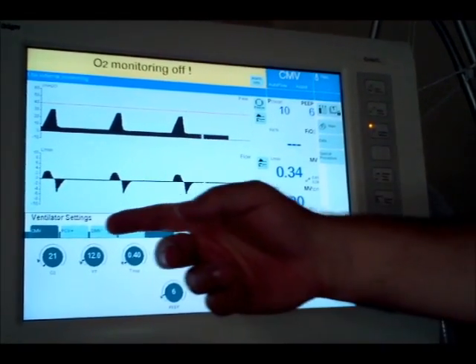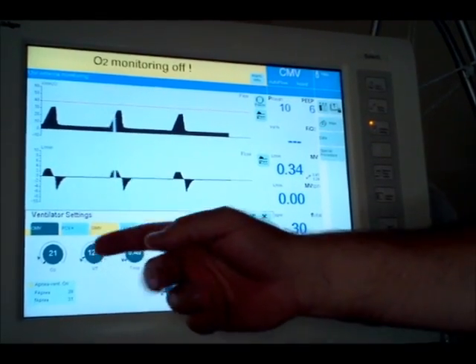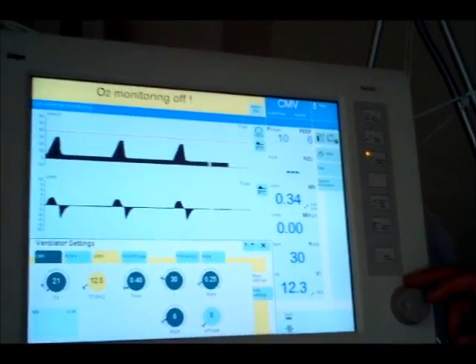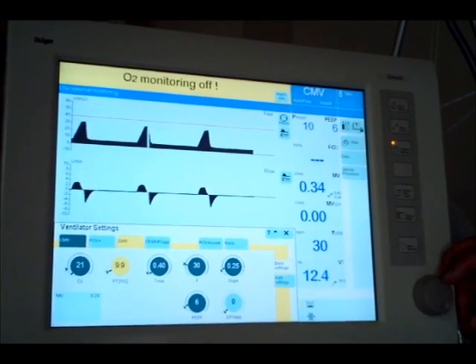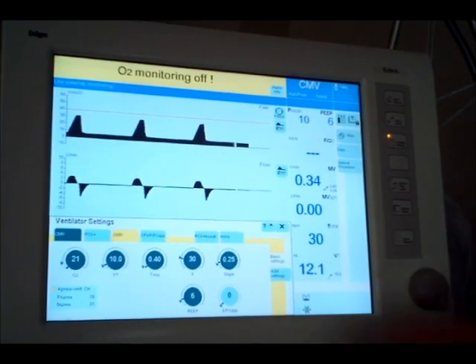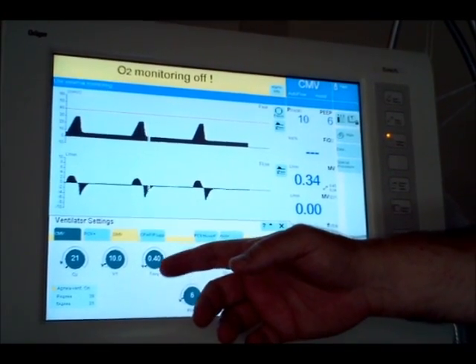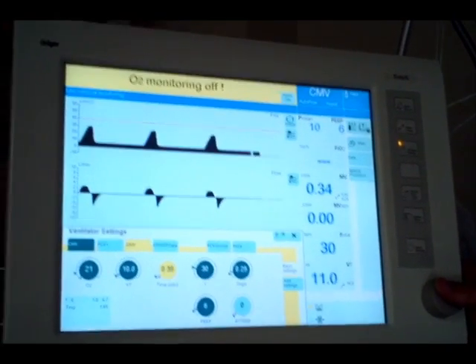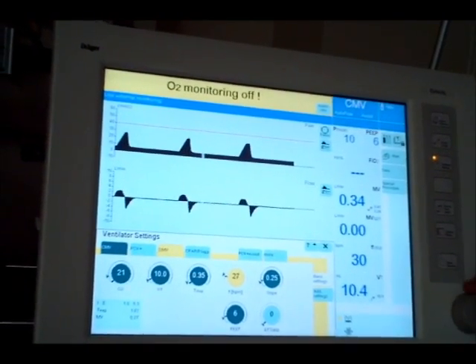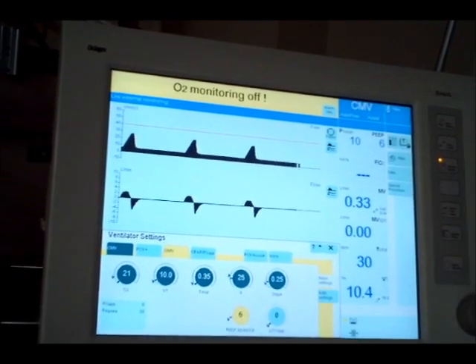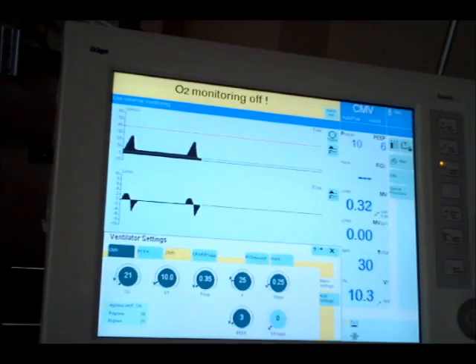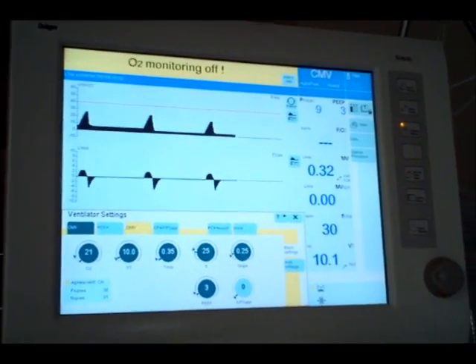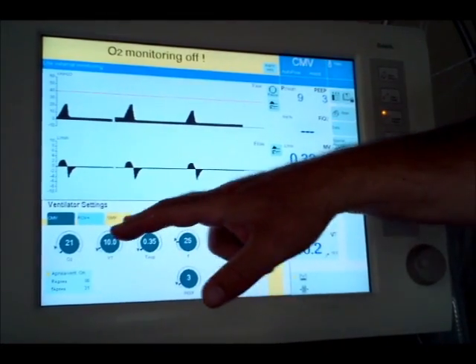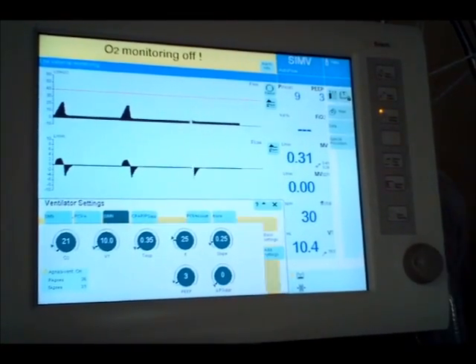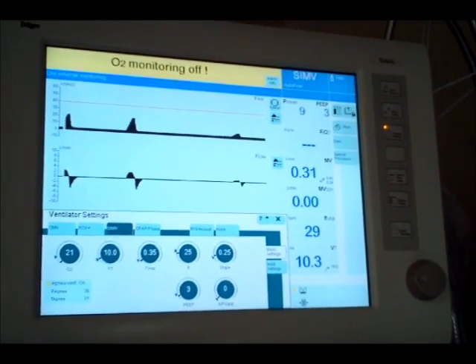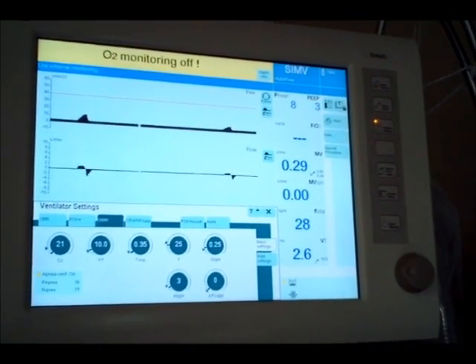Spent too much time talking. I don't have the yellowness anymore. So tidal volume 10. And that changed. Did I say 0.35? I'm trying to go by memory. Yes. 25. Yes. I said 3 here. Yep. Okay. This is where if you try to do it that way, this is where it gets tricky. Make sure I still have not changed the SIMV mode, so make sure you still confirm it that last time. Okay. Now I'm in SIMV. With my new settings.